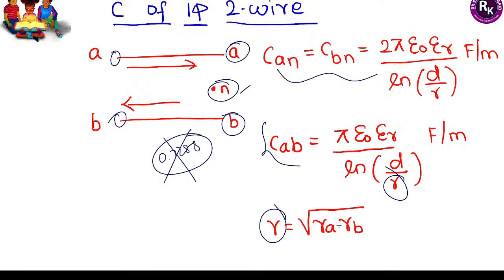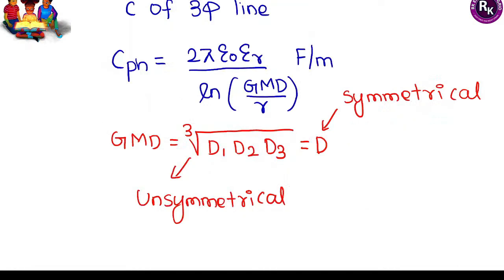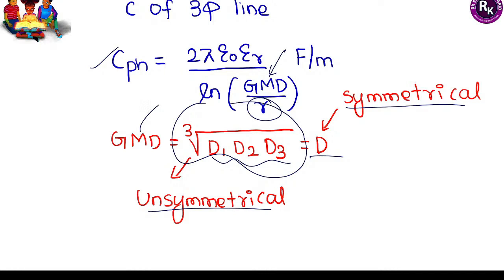For capacitance with two conductors having the same radius, ra equals rb equals r, so under the square root r² simplifies to r. The formula's D is essentially GMD and the denominator is GMR, but since self-GMD is not used for capacitance, we directly take the radius without the 0.7788 factor. For a three-phase line, the conductor radius is directly substituted; for symmetrical configuration, the cube root simplifies to d; for asymmetrical, the GMD formula must be applied.